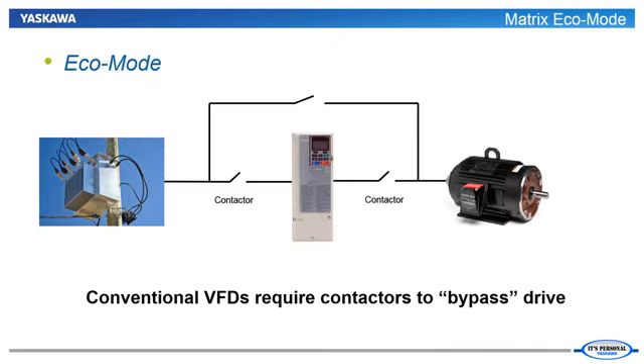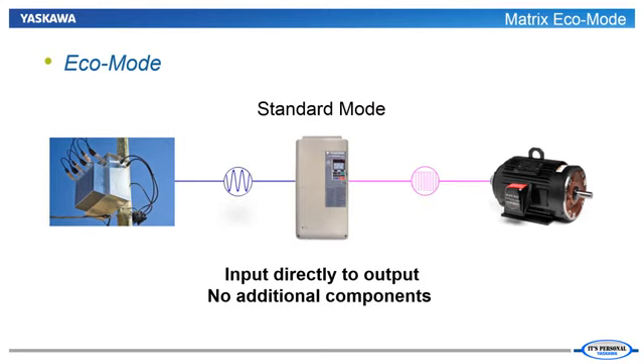Now we can discuss the eco mode. Sometimes the benefits of being able to vary the speed of the fan or pump are lost because the application is demanding full speed or near full speed operation. During these conditions, it would be nice if we could just open and close some contactors in order to shunt around the drive, bypassing it, and run off line power. The matrix drive takes the concept of a bypass and integrates it into its control to automatically switch back and forth between drive control and operating the motor using line power directly. This is called eco mode.